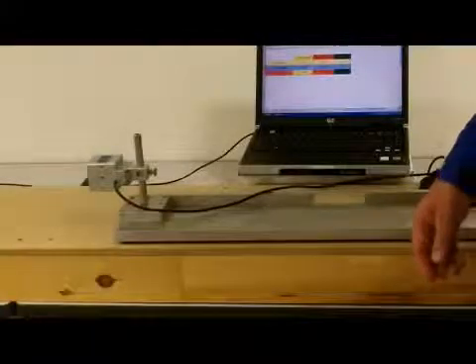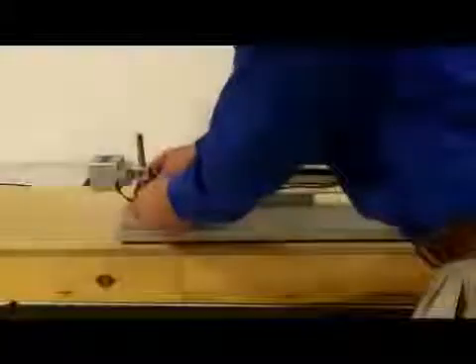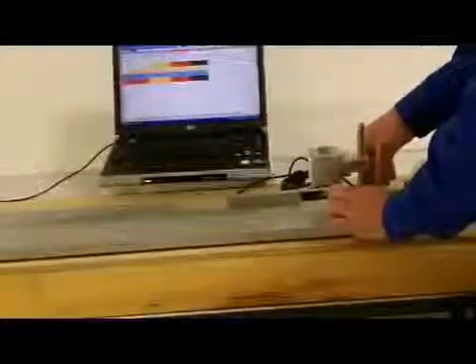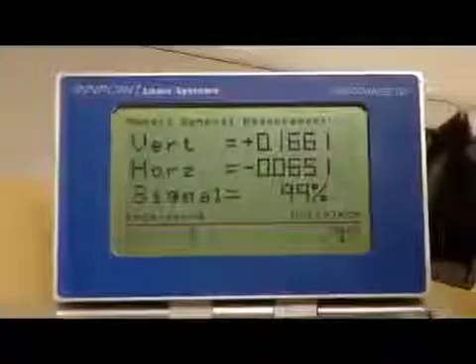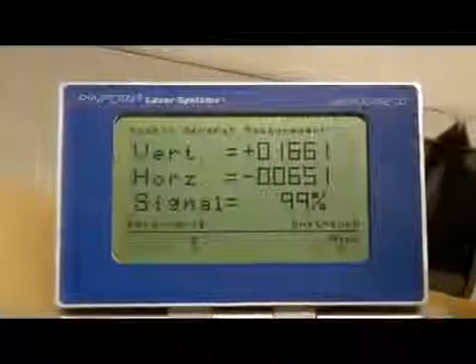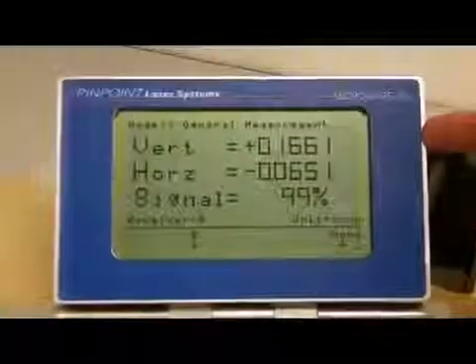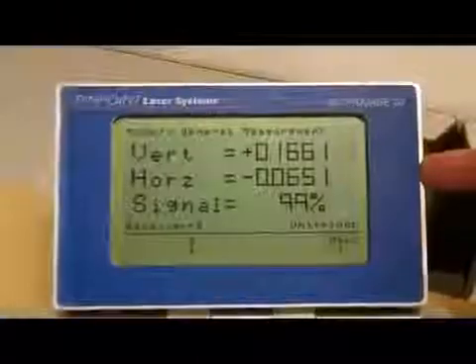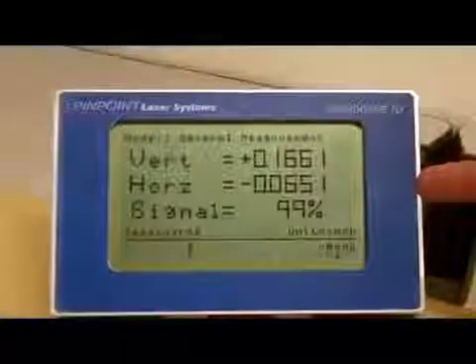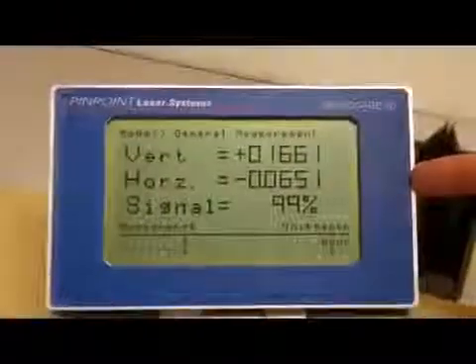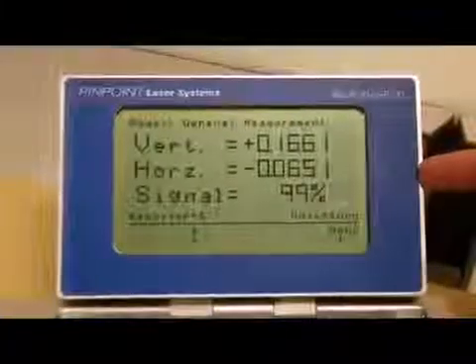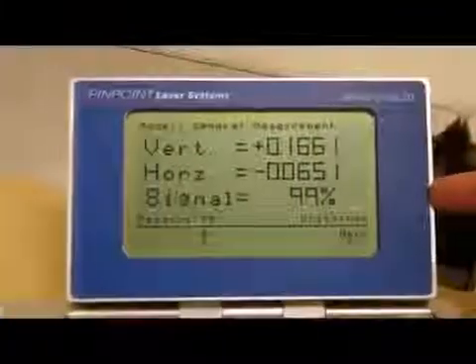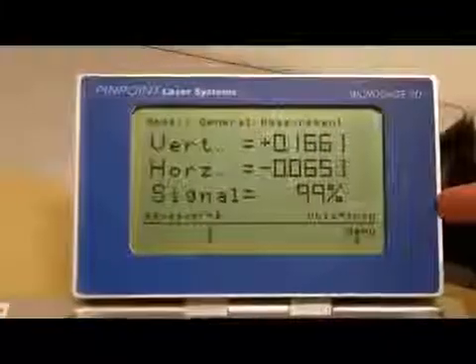Now I will move my receiver back to location number two which is in the back of my rail. And I will observe the readings now on my display unit. Again the readings for location two are clearly displayed on my display unit. I have a vertical reading of positive 0.1661, horizontal reading of minus 0.0651, and again a strong signal strength.